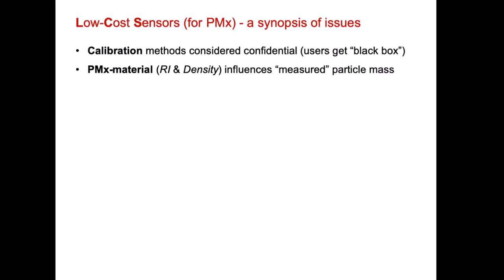We also don't know the RI, the refractive index, which also influences the measured mass. However, the refractive index, I wouldn't say it's less important, but it influences nephelometric measurement, where we measure light scattered from many particles at once, less strongly than it does single particle measurement. And the signals are more stable the more polydispersed the particle material is.